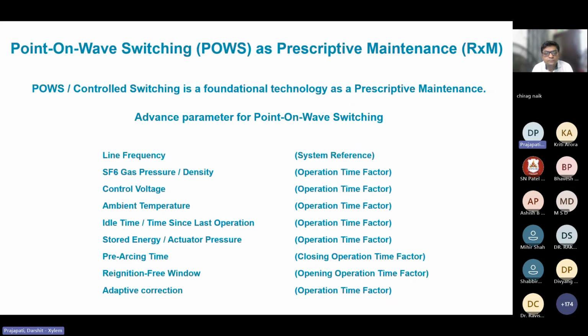So you are targeting the peak of the wave to close. But if arcing is present previously, like if pre-arcing has happened, then the electrical contact happens earlier than the peak, and then there will be consequences and stresses on the contact. Similarly, there will be a reignition-free window that we need to ensure for the opening operation. So all this will have an impact on the operating time delay, which will be introduced by the point on wave switching device. And finally, the breaker will be operated at the target point, whether it is a zero crossing or the peak of the wave.